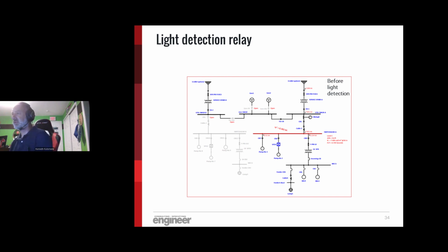So for this one, I know there are some questions of how you simulate some of these techniques in SKM or ETAP. In this case, the picture shows the 4160 gear. Under normal conditions, it's about an 8 cal incident energy level.